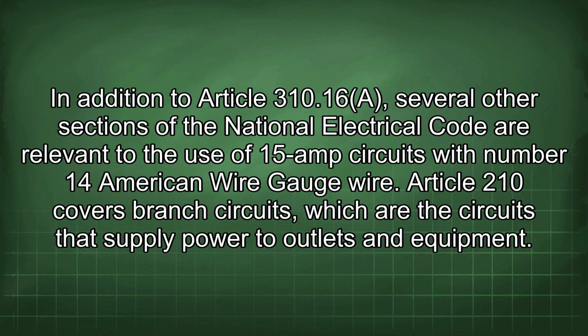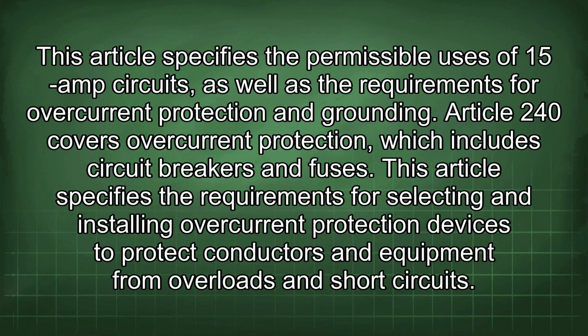In addition to Article 310.16a, several other sections of the National Electrical Code are relevant to the use of 15-amp circuits with number 14 American wire gauge wire. Article 210 covers branch circuits, which are the circuits that supply power to outlets and equipment. This article specifies the permissible uses of 15-amp circuits, as well as the requirements for overcurrent protection and grounding.